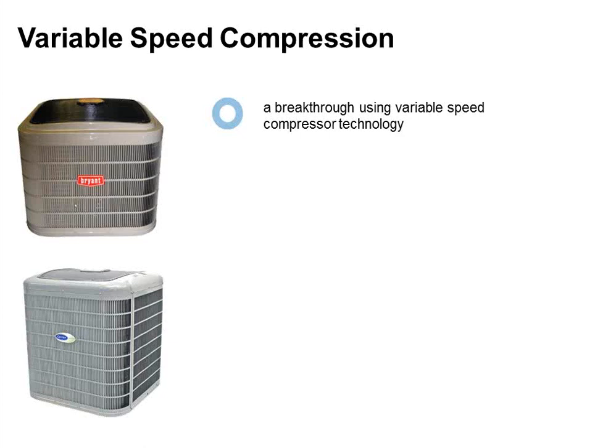What's really new here is that we're actually putting inverters on regular split systems that I can use in residential and light commercial, as opposed to a duct-free split style unit. So these are these two heat pumps. The HSPF is extremely high. It is higher than any manufacturer in the world. It's 13 HSPF. That's heating seasonal performance factor. That is basically the energy rating for these units. So it's kind of like the SEER, but on the heating side. We'll talk more about that as we go.